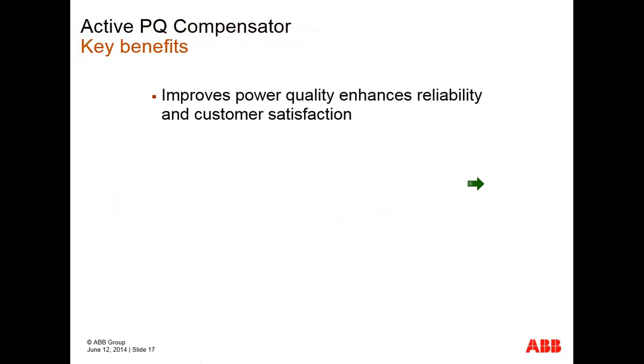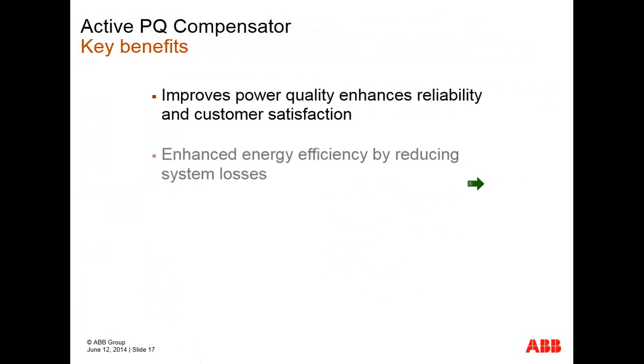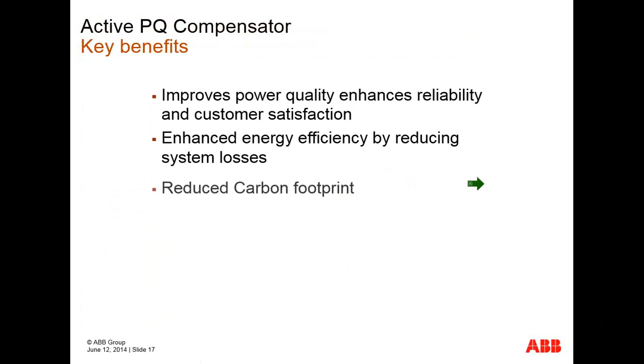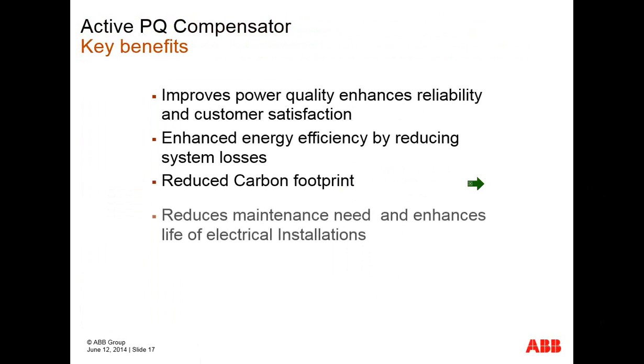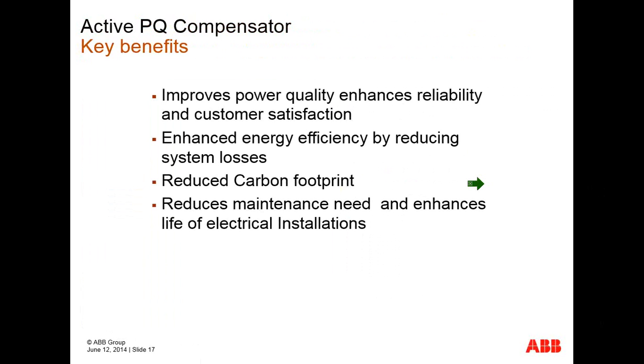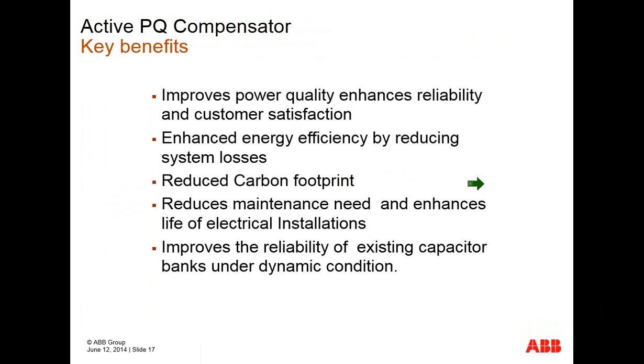The key benefit is the objective to improve power quality, enhance reliability to the end user, enhance energy efficiency by reducing system losses, reduce carbon footprint, reduce the maintenance need and enhance the life of electrical installation. And finally, improve the reliability of the existing capacitor bank, which under dynamic condition was not able to meet the desired requirement. And there is no risk of resonance or harmonic amplification, because this is an active-based compensator, so it does not consist of an inductor-capacitor solution, which is passive.